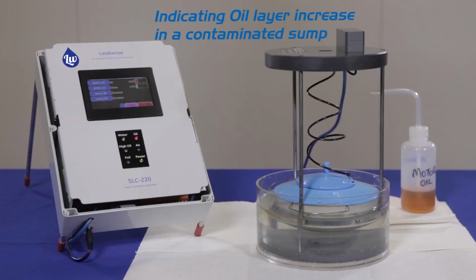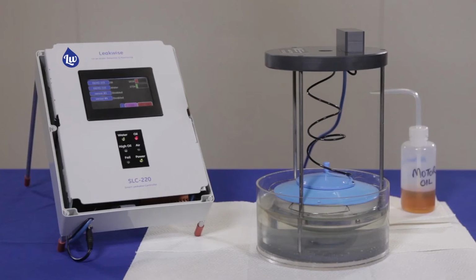Some customers have sumps that have oil already in there, and that's always there. What they need to know is when that starts to change, when that starts to increase. What we can do with this technology is we can call that background layer 0. And we can do that simply by recalibrating our controller to that value.